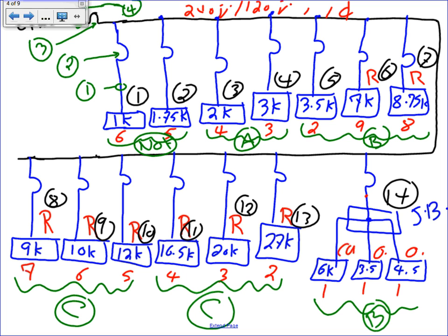Why is that? Why wouldn't they read the column A? Because if you read Article 220.55, it will tell you that the table applies for anything larger than 1.75. If it's less than 1.75, it doesn't apply. So we're going to mess with them right from the get-go.